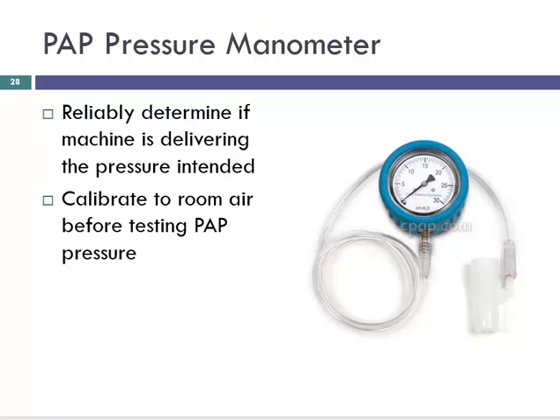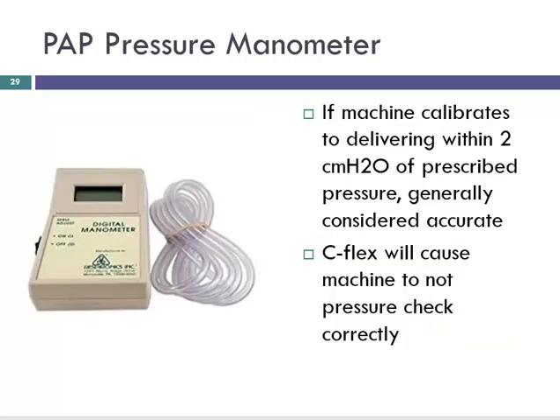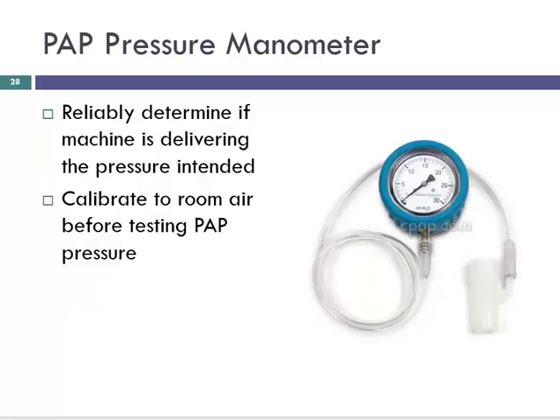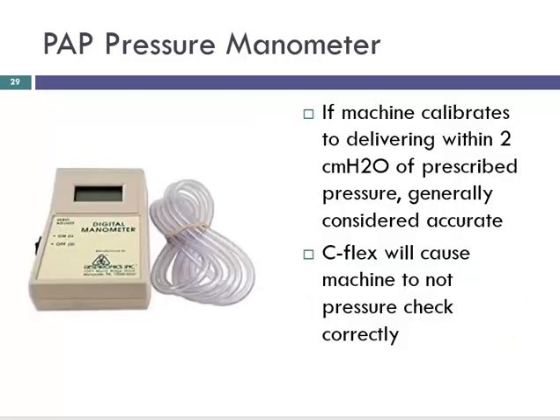Part of our job is testing the pressures of the machines, to test the integrity of the machines, and we can do that through a manometer. Essentially you hook it up to the end of a machine and you occlude it, and say the machine is set at a CPAP of 10, you just want to see the manometer read 10. If it's more than 2 centimeters of water pressure off, it means the machine is no longer delivering the pressure it's set to deliver, and it might be time to take it out of commission. We routinely, I think monthly, calibrate our machines and test them to make sure they're delivering the pressure they're set to deliver. This one is an analog version of the manometer. This one's digital, where you get an actual number readout. Basically, as long as it's within 2 centimeters of water pressure of what it's supposed to deliver.